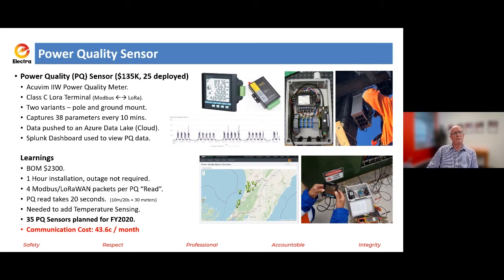What we discovered: BOM price is about $2,300, which is not cheap, but $2,000 of that is effectively the meter. It doesn't take long to install, only an hour. It takes 4 Modbus packets to do a read of data, which takes about 20 seconds. So if you do the sums, we can only fit about 30 meters and 30 requests into a 10-minute period, and currently we're reading every 10 minutes.